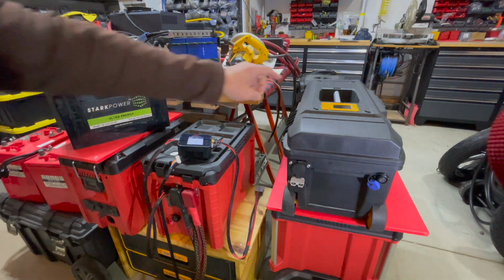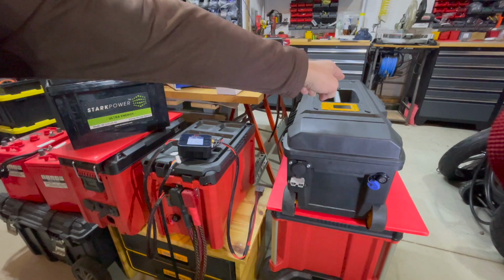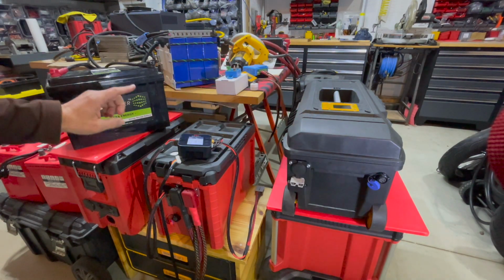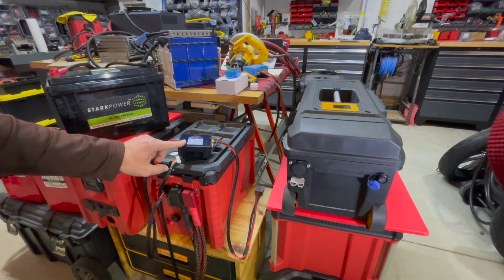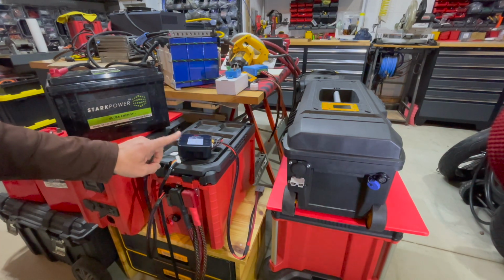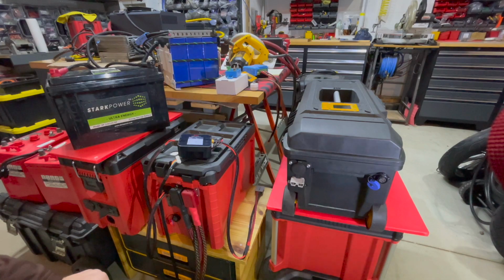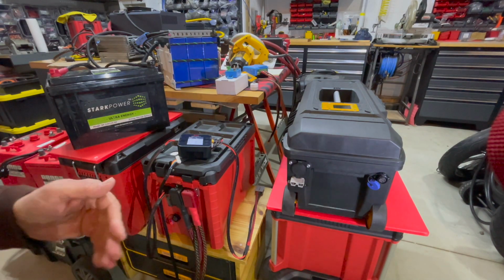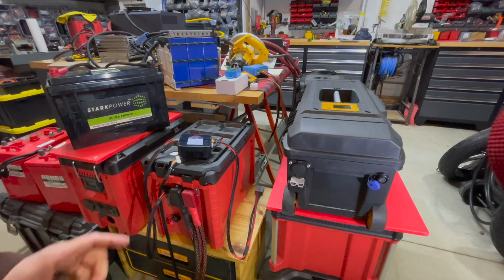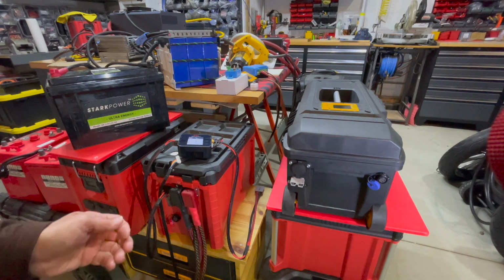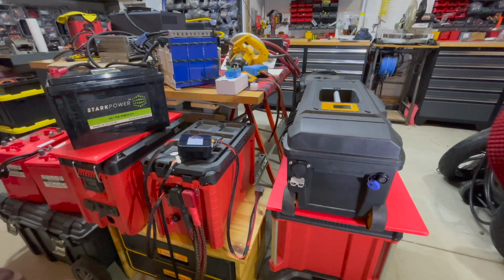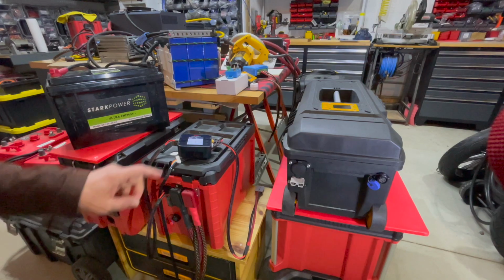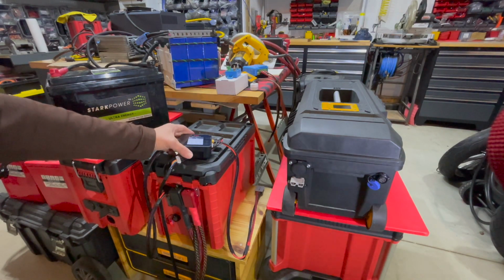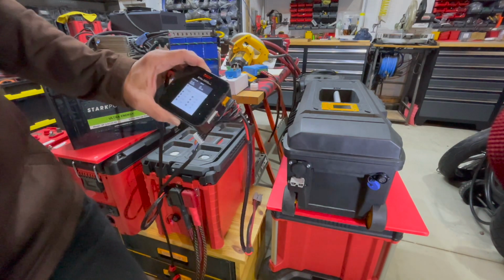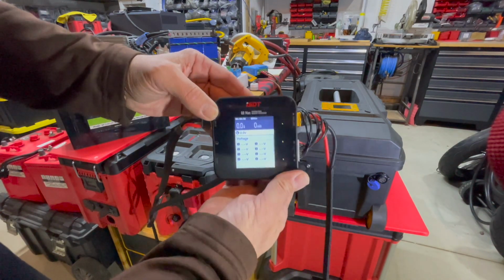This one here is set at 3.6, and the failsafe is set at 3.65. So I want this charge controller to not just shut off at 3.55, but to slow the charge down when it hits 3.5 volts, to say 5 or 10 amps, to allow the battery to float or absorb, and get all the cells up to that 3.55. It also has a balancer as well. I'll bring this up to the camera to give you an idea - it's reading at 0 right now.